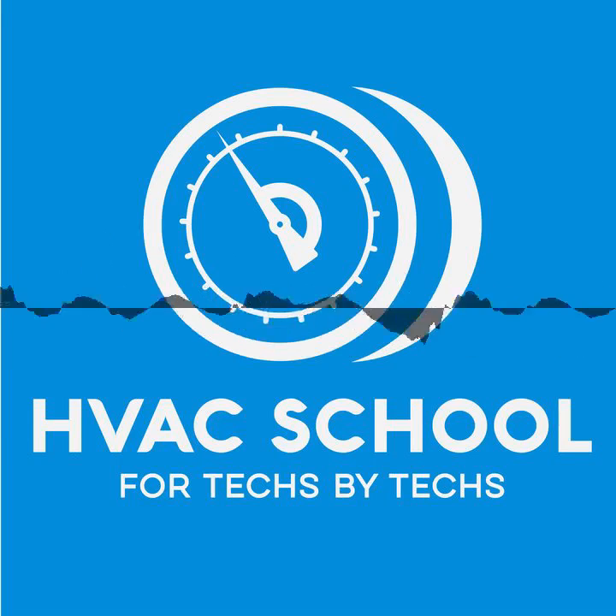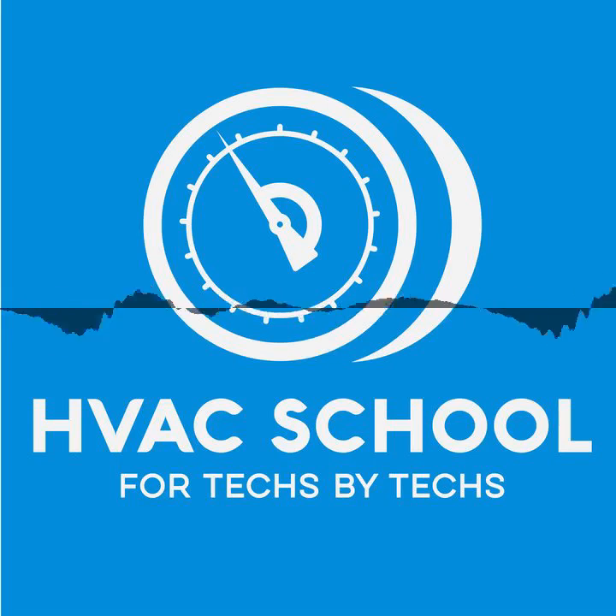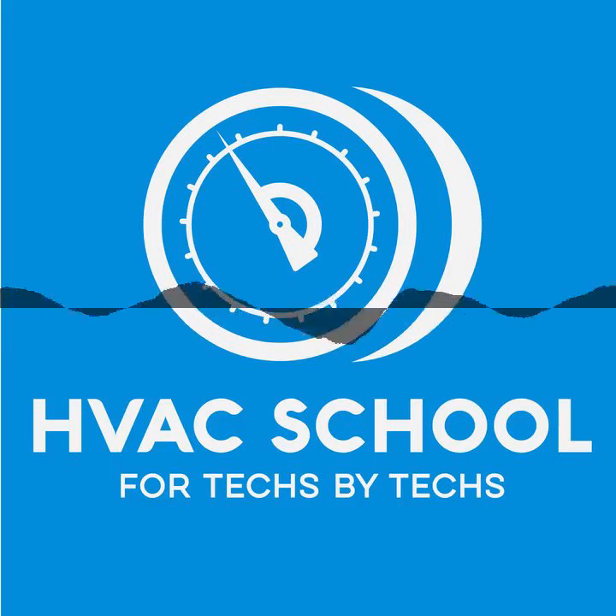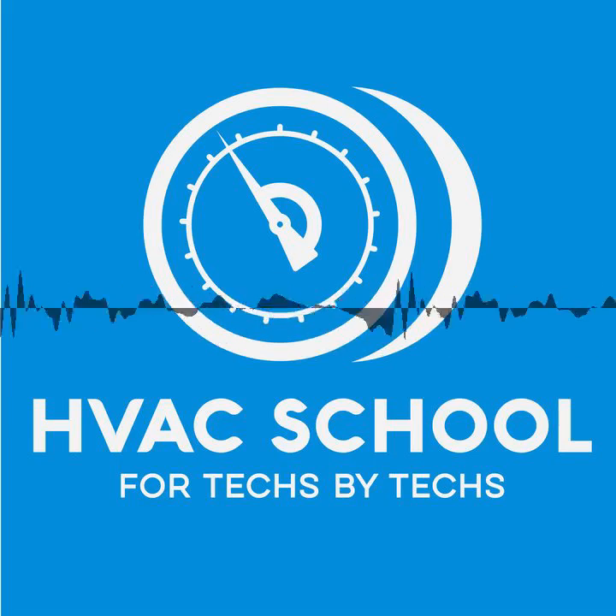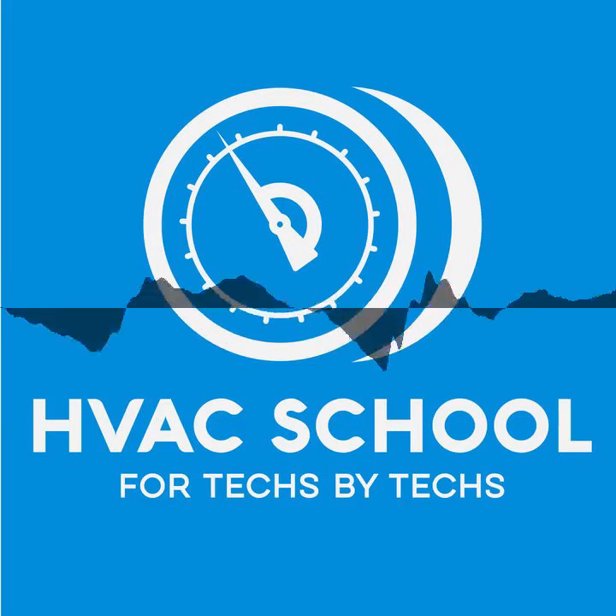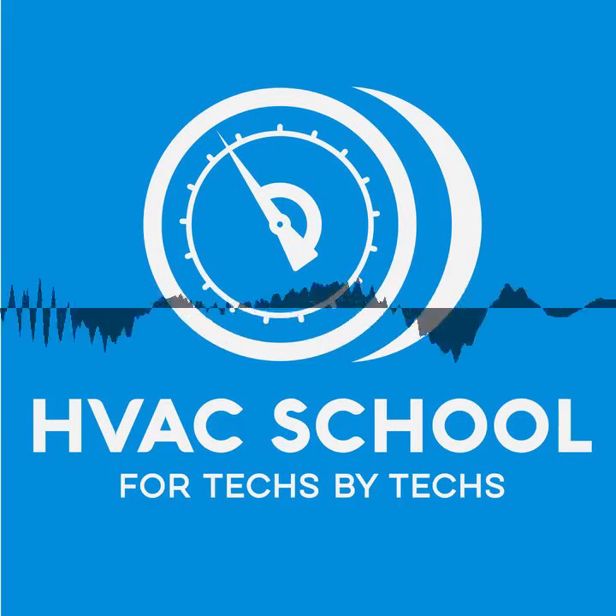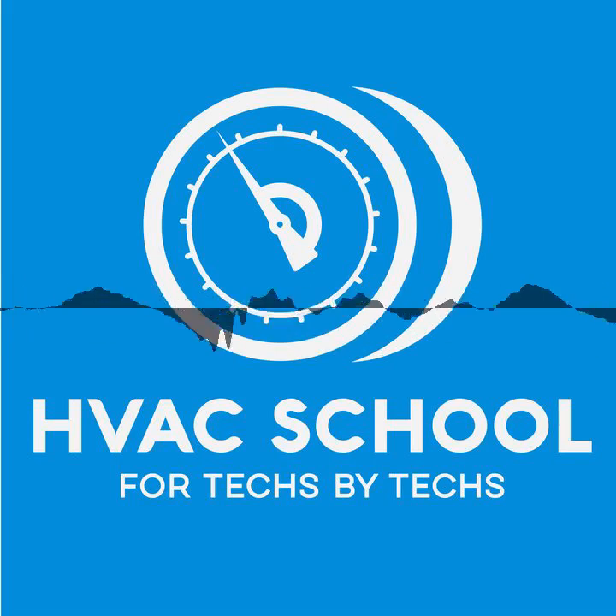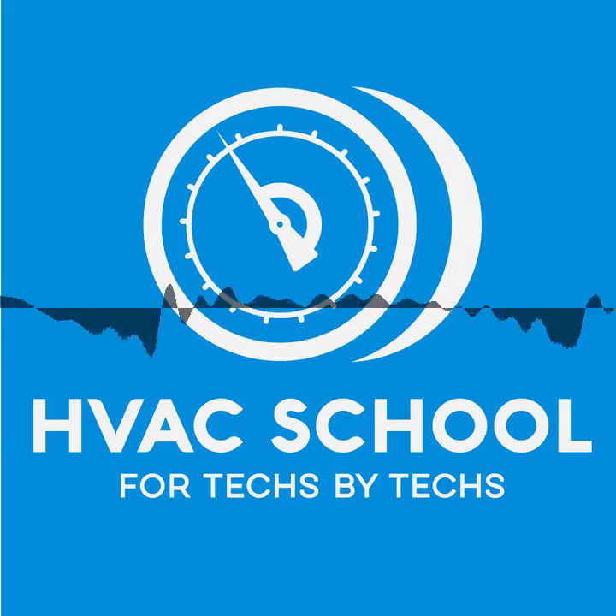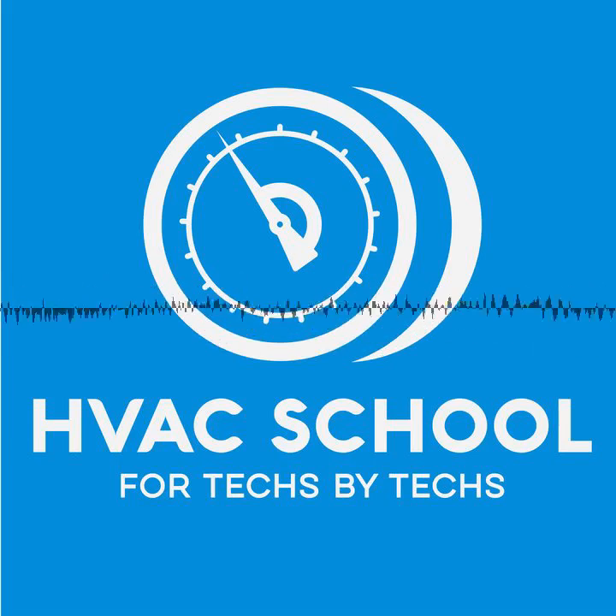And it also has the additional port for the vacuum. So if you're gonna pull a vacuum through your manifold, I think the 557 is probably the best option. And again, this is my opinion. I'm not saying there's anything wrong with the other brands per se, but for this reason, I think this makes it superior. Now, again, we don't even suggest you pull a vacuum through your gauges, and so you can still use the 557 without pulling through it if you want. You can still use the micron gauge on it. You just aren't going to have your hoses connected to the system anymore. So I know that's a little bit confusing.